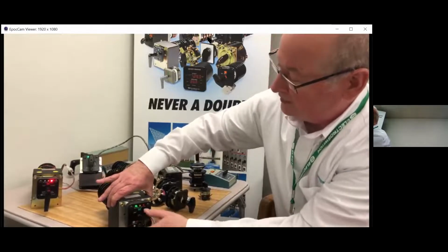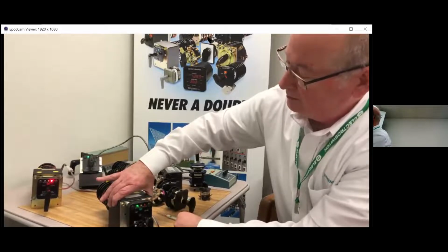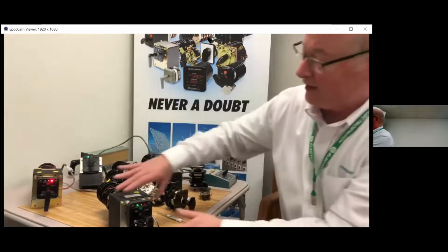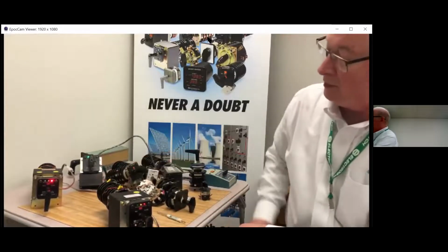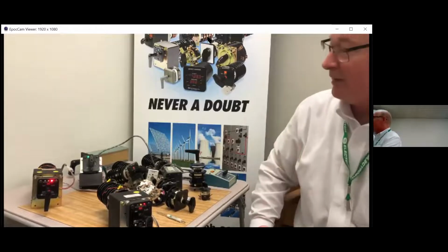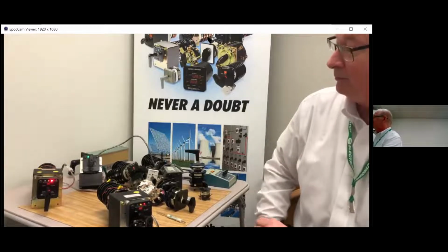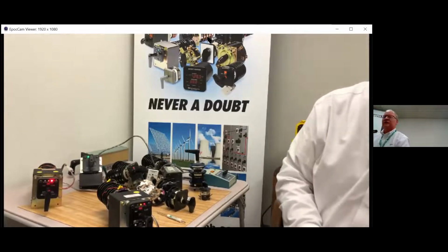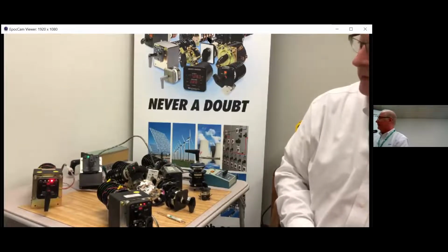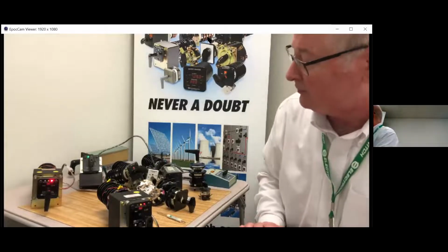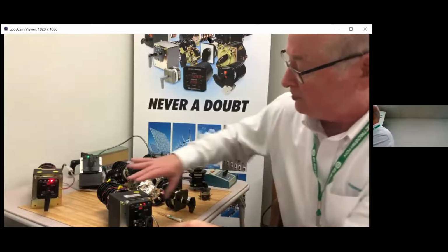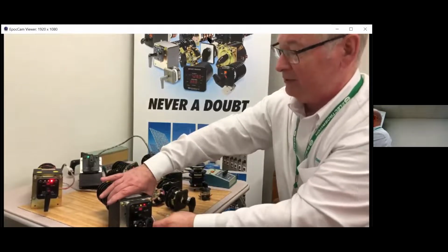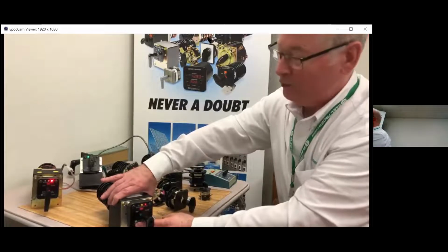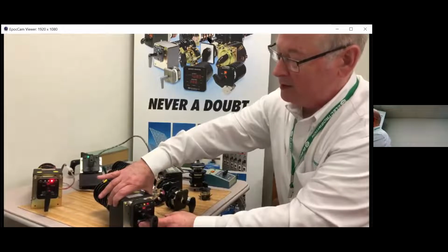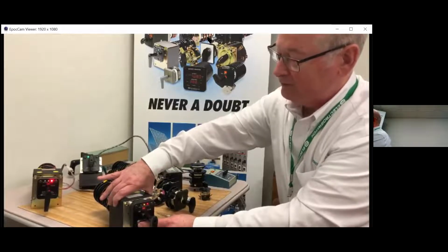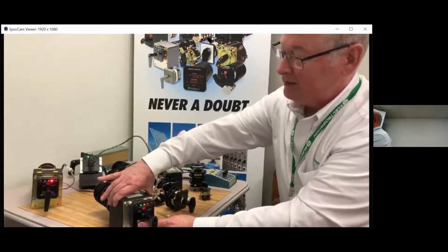So if I have a breaker that is operating fine, and I go ahead and close the breaker, I've got my indication on, and I'm ready to come into a substation room, and I want to set the trip function on this. I go up to this control panel and I want to do a delayed open. So while I'm sitting here, this happens to be a 10-second delay open control switch TDCSR. So what I do is I press the button and hold it for 4 seconds, and I'm going to get an LED that starts activating.